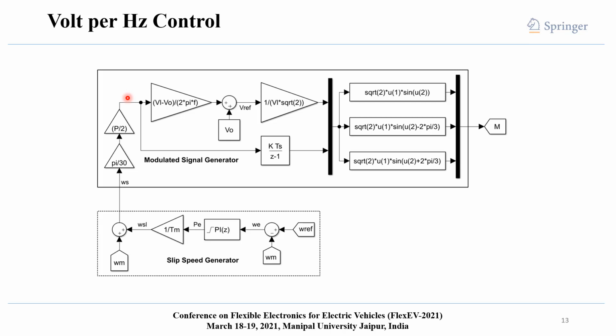After obtaining the electrical radian per second, it is converted to position by integration, and this electrical radian per second is multiplied with the rated V/F ratio to get the required voltage, which is added to the offset voltage to start the motor from stationary.